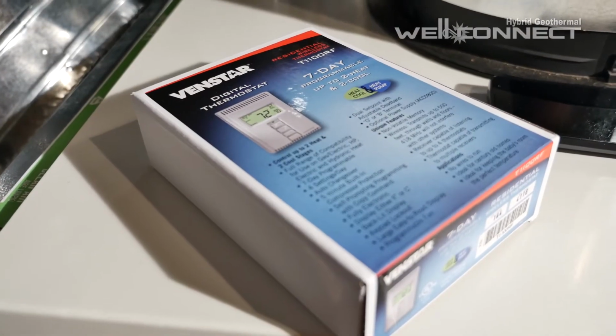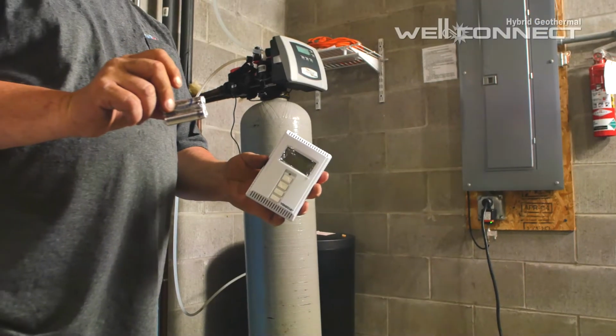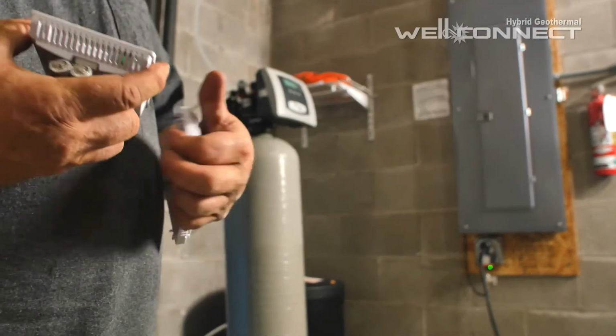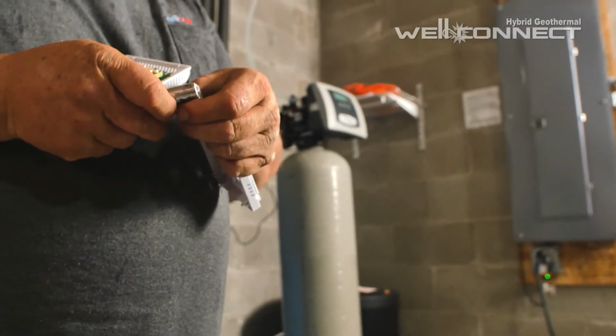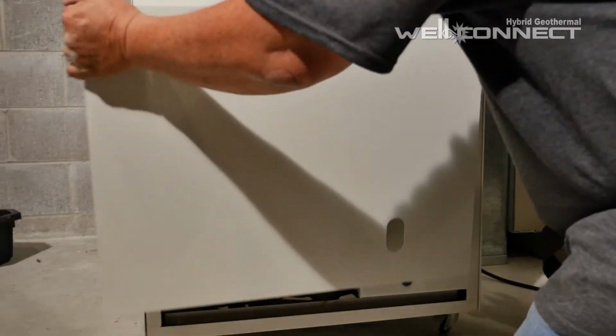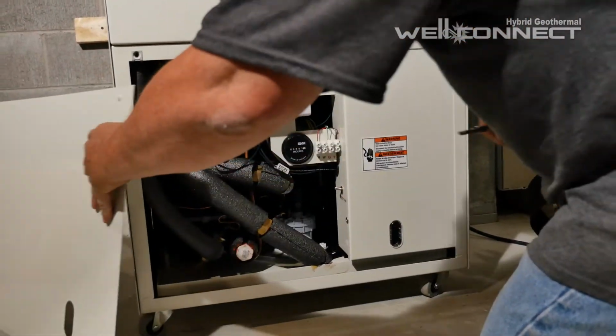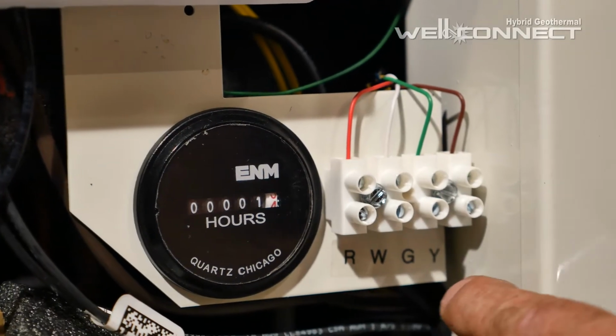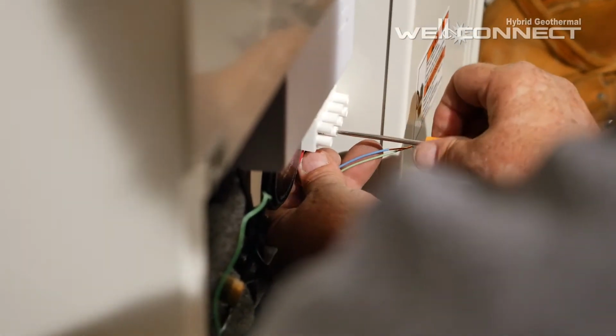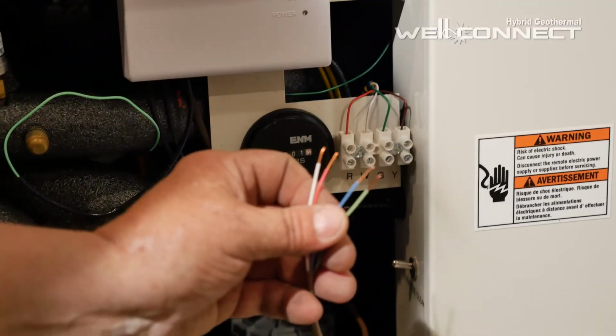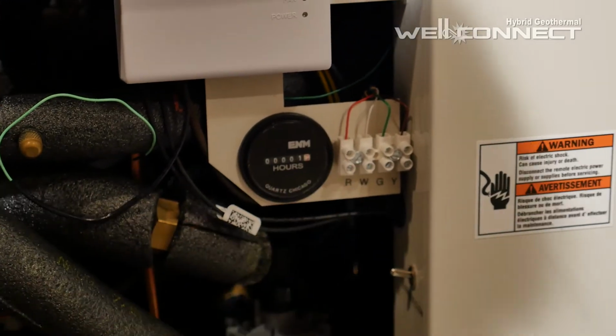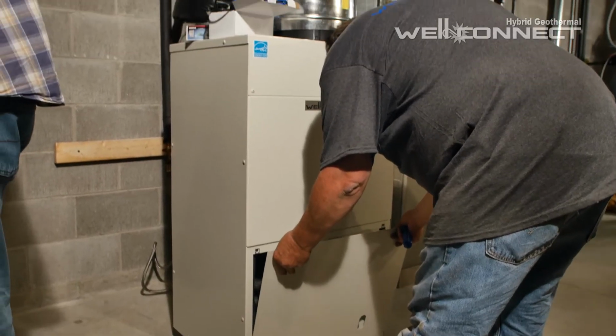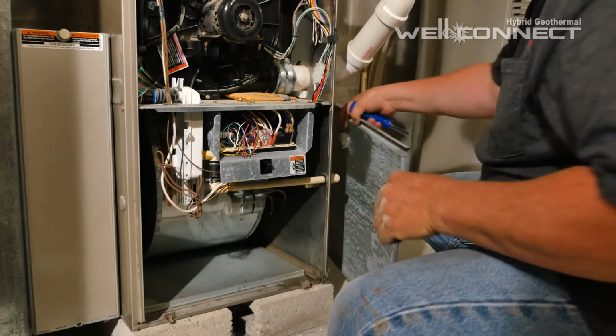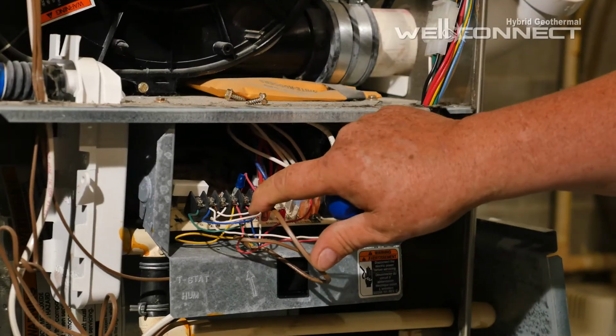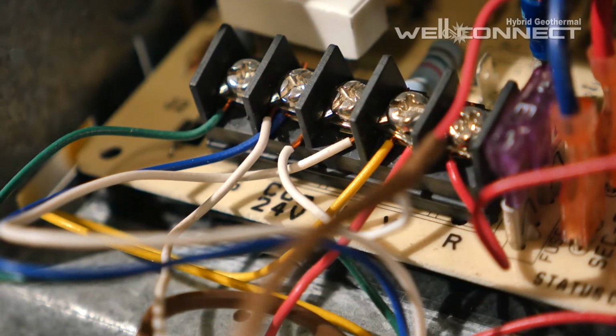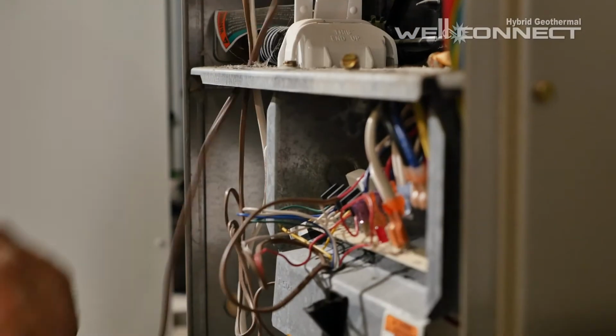The Well Connect's wireless thermostat will control the Well Connect to provide first stage heating and cooling, and the existing equipment to provide second stage or supplemental heating and cooling only when needed. To enable this two-stage control function, a piece of 4-conductor thermostat wire must be run from the color-coded terminal board found behind the front service panel of the Well Connect to the matching terminals in the existing furnace. For both two-stage heating and two-stage cooling, all 4 wires must be connected. For two-stage heating only, just the red and white terminals need to be connected. Do not remove any existing wires on the furnace terminal board.